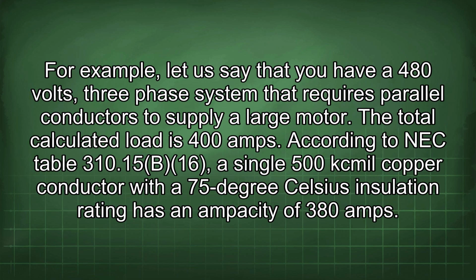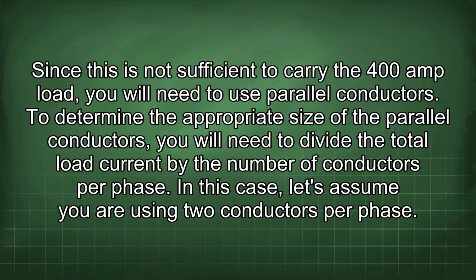For example, let us say that you have a 480 volts, 3-phase system that requires parallel conductors to supply a large motor. The total calculated load is 400 amps. According to NEC Table 310.15(B)(16), a single 500 kcmil copper conductor with a 75 degrees Celsius insulation rating has an ampacity of 380 amps. Since this is not sufficient to carry the 400 amp load, you will need to use parallel conductors.